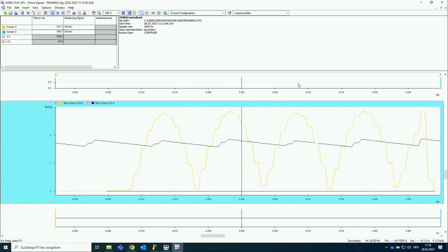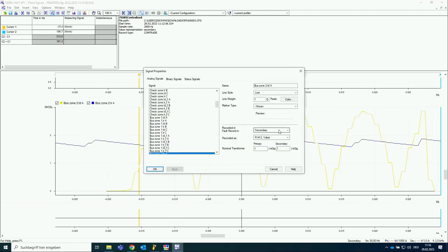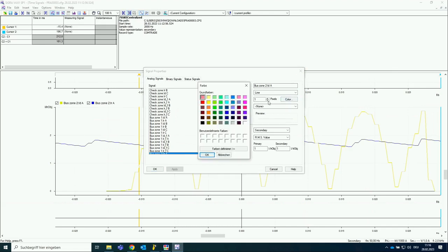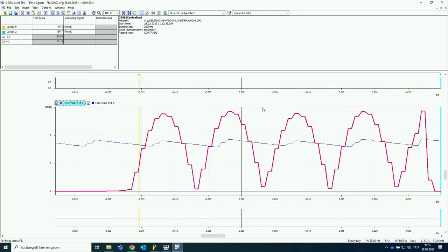So now we can analyze the 2 out of 2 algorithm. If you remember correctly, the 2 out of 2 algorithm will be triggered for the first threshold exceeding when the 1 out of 1 algorithm can't apply. That means we have no jump of the stabilization current. The stabilization current is the blue one, and I think it's very clear that we have absolutely no jump of stabilization current. So a 1 out of 1 algorithm is not possible.